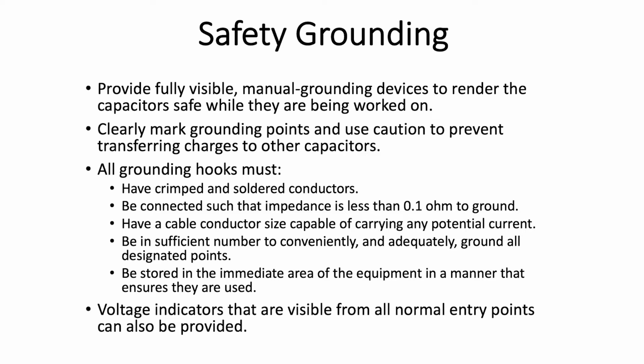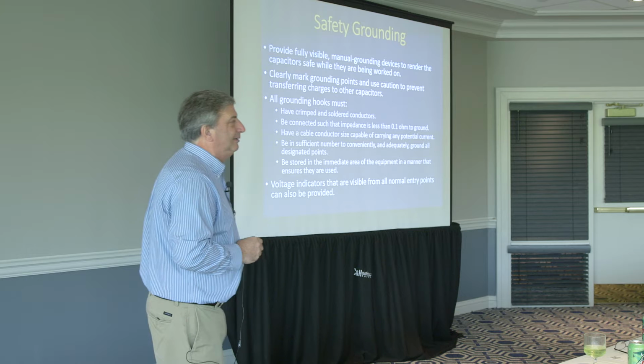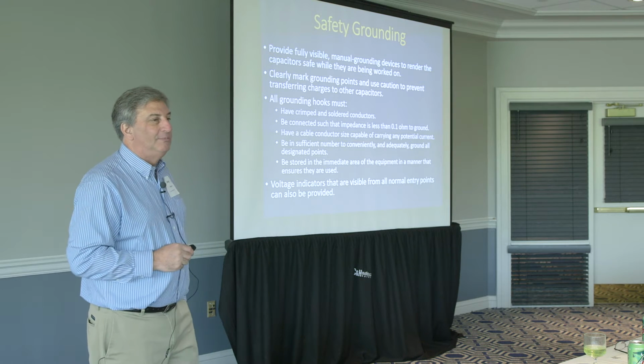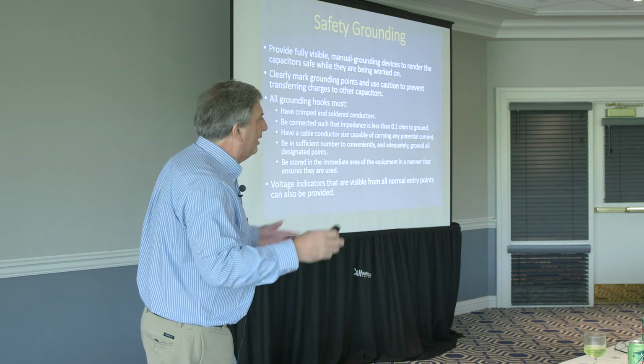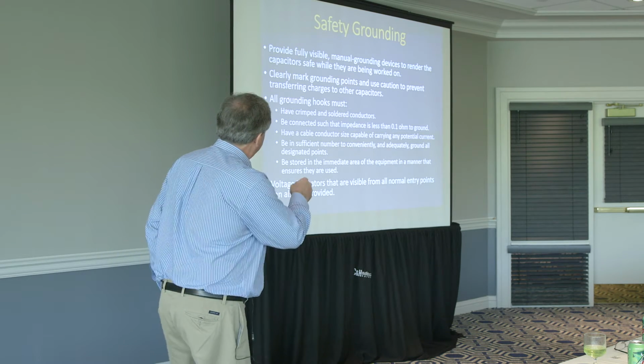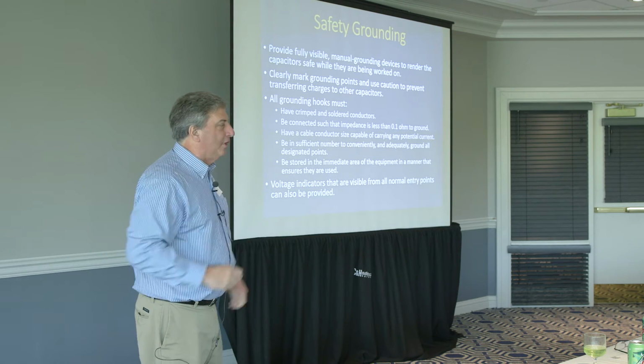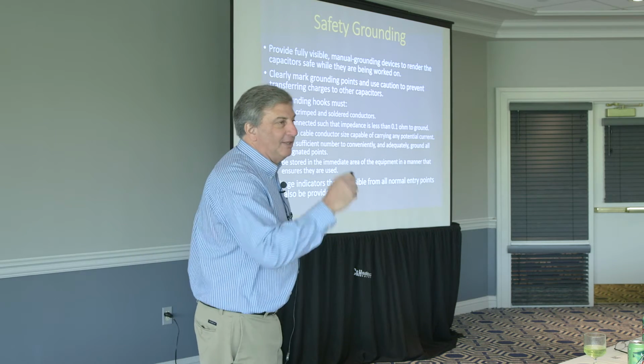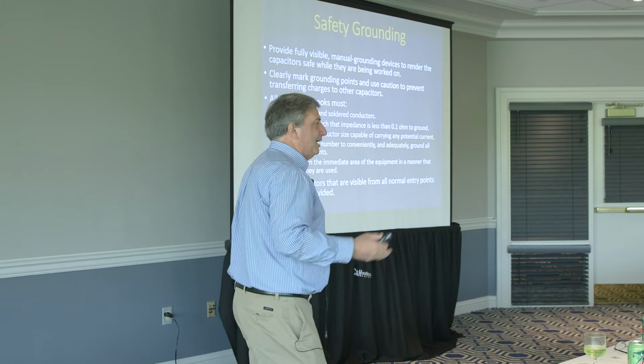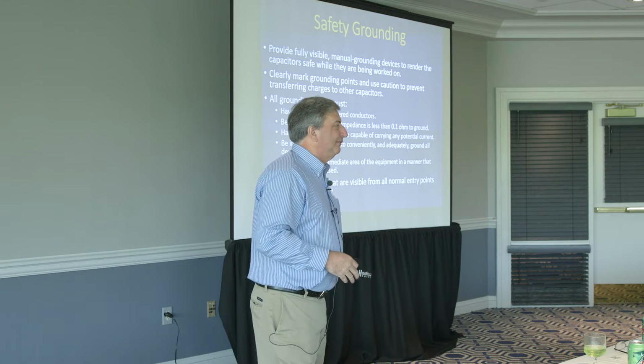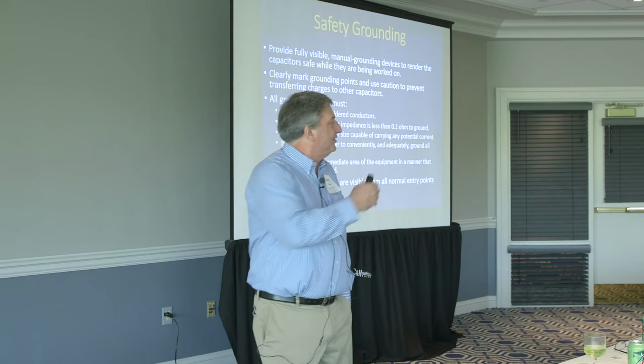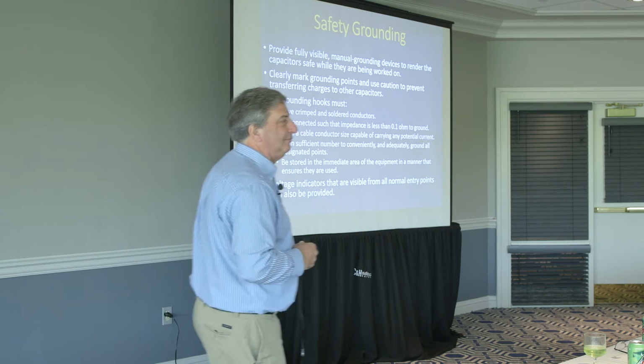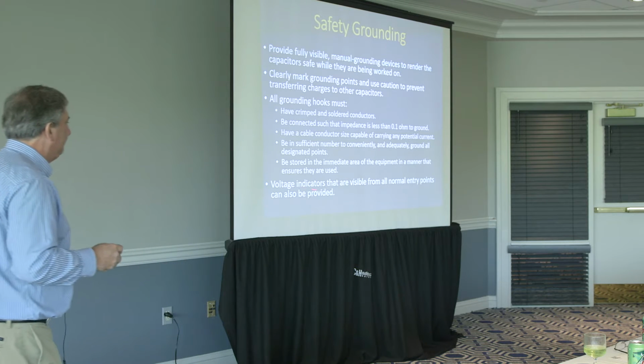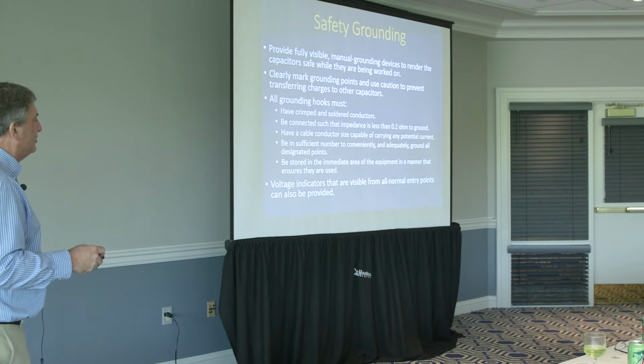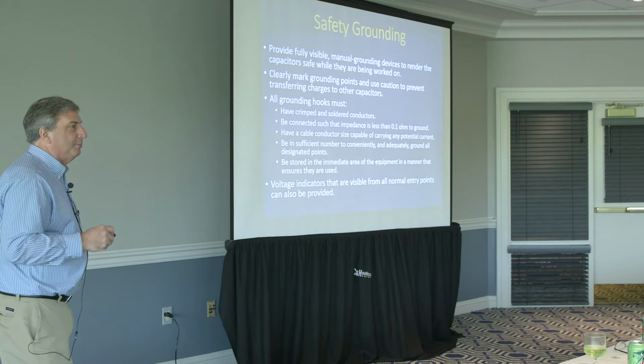OSHA inspectors have checklists. If you get a surprise inspection, in terms of your capacitor room or the place where that cap bank is, these are the things they're going to look for and check. And if they get all the checks, you've done that, okay, fine. It doesn't matter if there's bad connections or other types of things. This is what they're looking for. That will get you a fine. Voltage indicators that are visible from all normal entry points can also be provided.